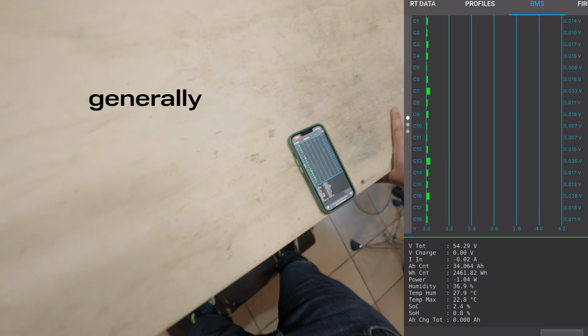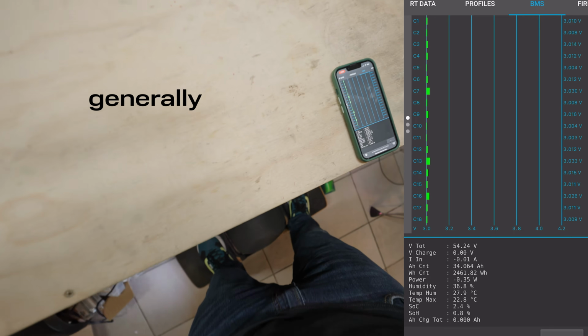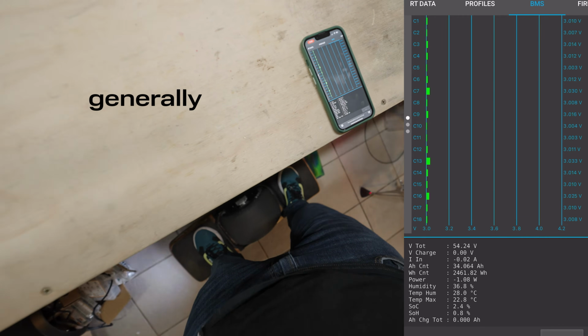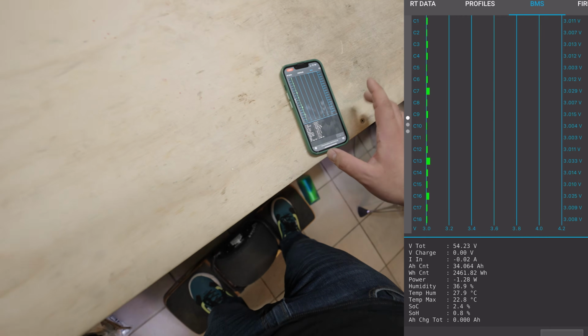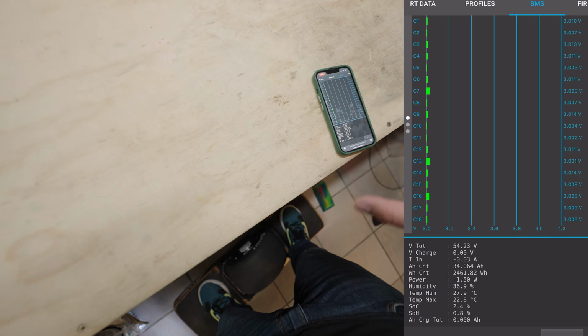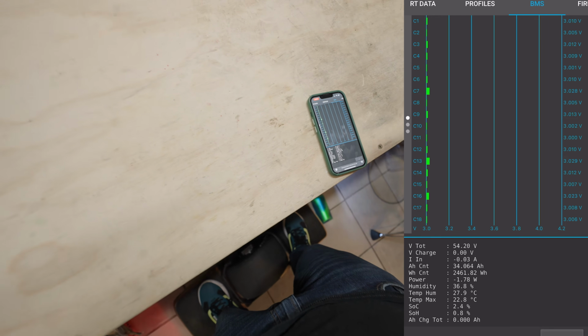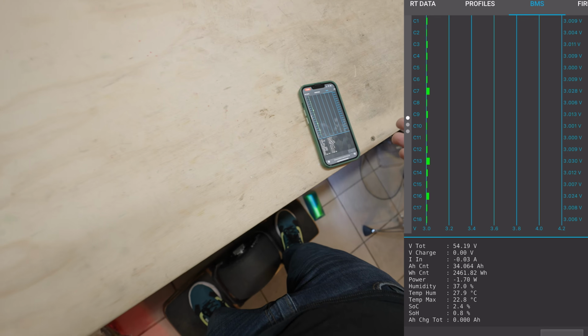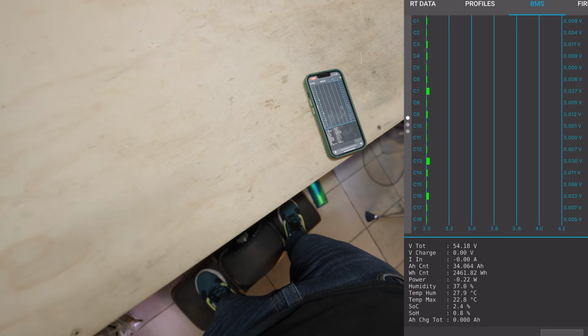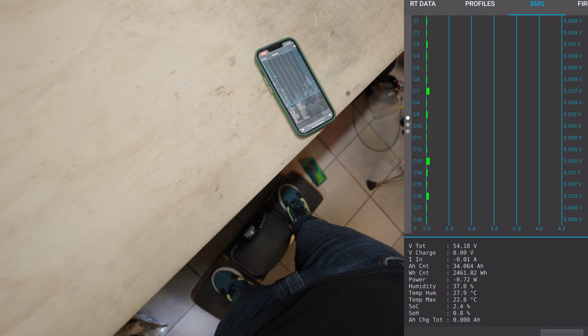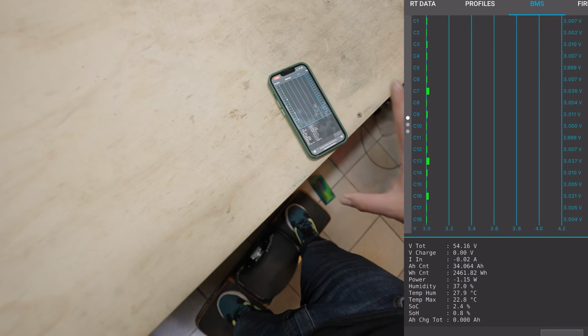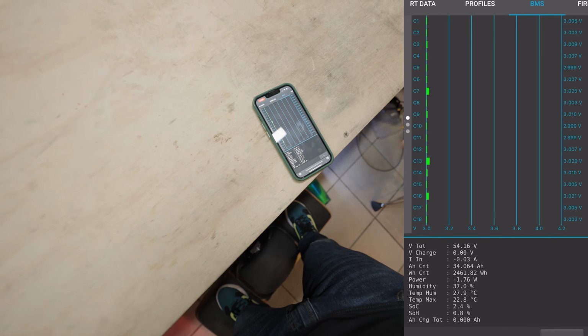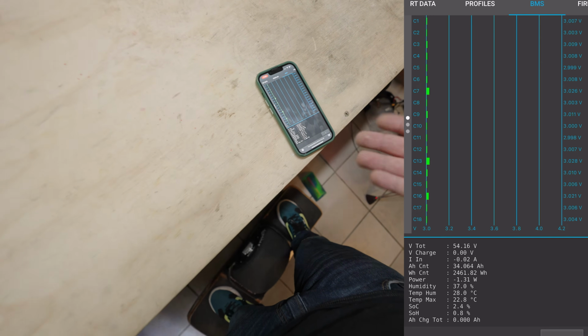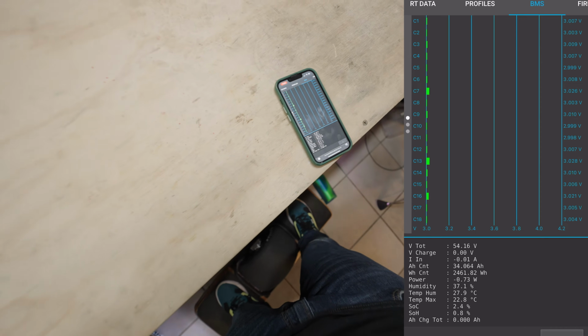No one would actually ride past this point. So even with an uneven spread, if you're hitting this point, you've reached the end of your charge. Even if you wanted to ride down to 2.7 volts per cell, you wouldn't get much out of it because there's not much energy down there, and the battery would start to sag under load and reach your low voltage cutoff anyway.